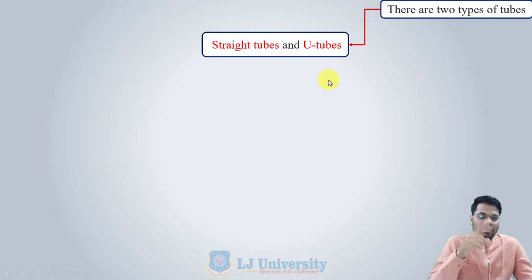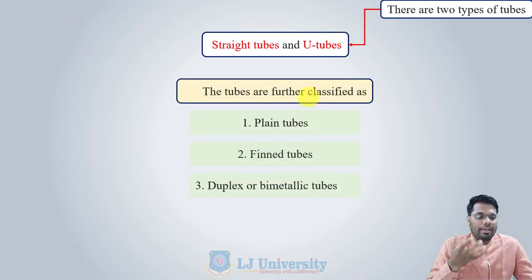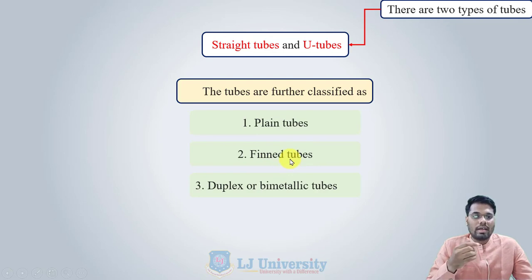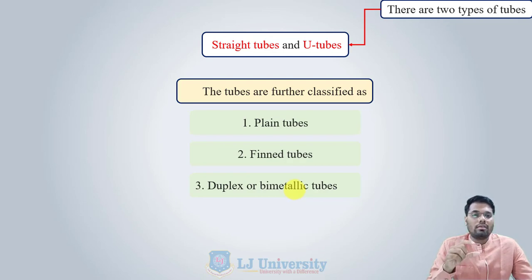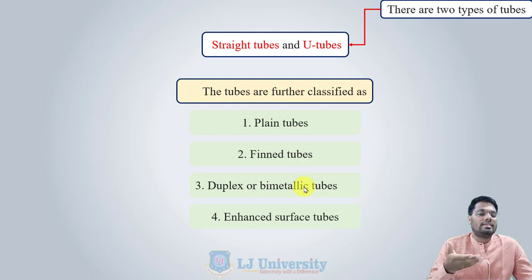There are generally two types of tubes — straight tubes and U-tubes — but they can be further classified into plain tubes, finned tubes, and duplex or bimetallic tubes. Plain tubes have no extended surface or fins. Finned tubes have extra or enhanced surface on the outer surface. Duplex or bimetallic tubes are used for special applications where both the outer and inner surfaces are provided separate coatings to withstand corrosiveness or fouling.